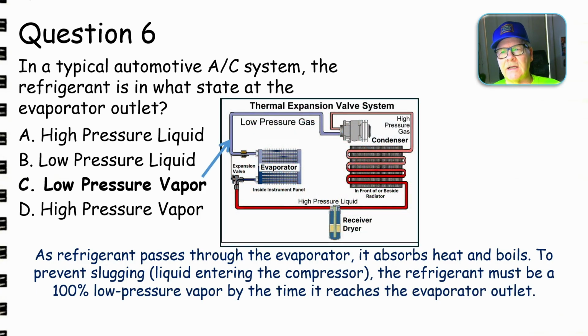Remember, I told you it needs to be cold. It needs to be cold all the way to the compressor. Now it's flowing this way. Discharge line is here, goes through the condenser, dumps the heat it picked up in the evaporator, goes through the receiver dryer. This is a thermal expansion valve system, so it's got a receiver dryer instead of an accumulator. And then it comes back through the expansion valve where it's throttled as it goes through the evaporator. If this gets too cold, it shuts that, it throttles that refrigerant, so there's not as much going through there. But it ought to be 100% low pressure vapor.